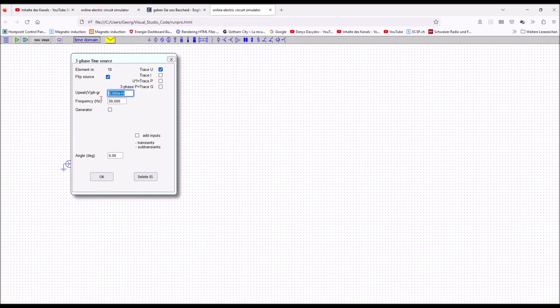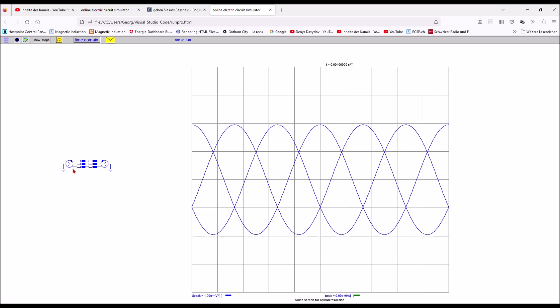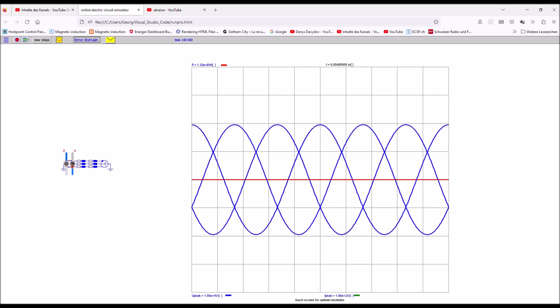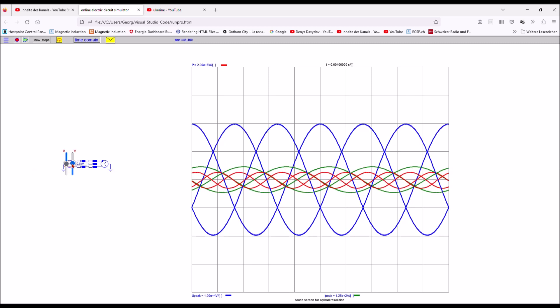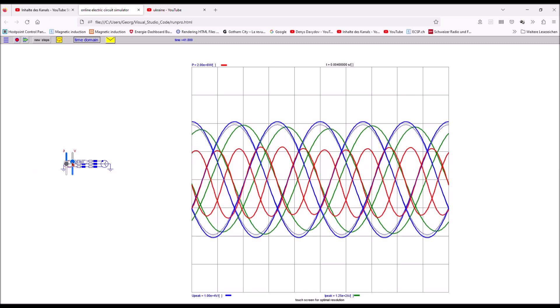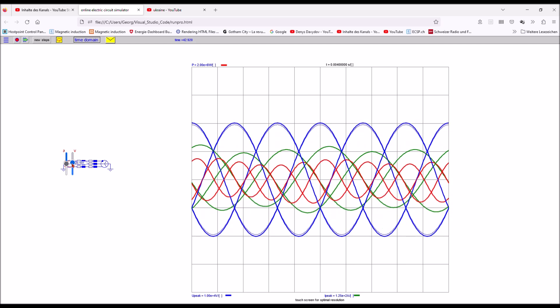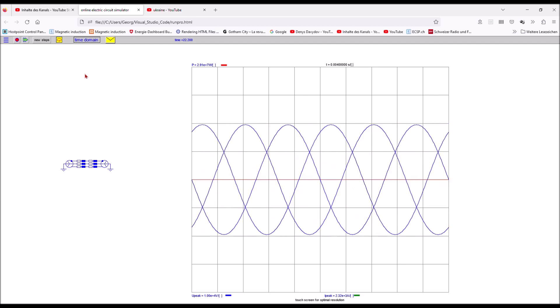If however the three phase voltages of the two generators are equal, logically no current flows and as a result there is no power flow. So no green current trace and no red power trace. If however I increase the voltage of the generator to the left then there is an imbalance, current flows and reactive power flows.